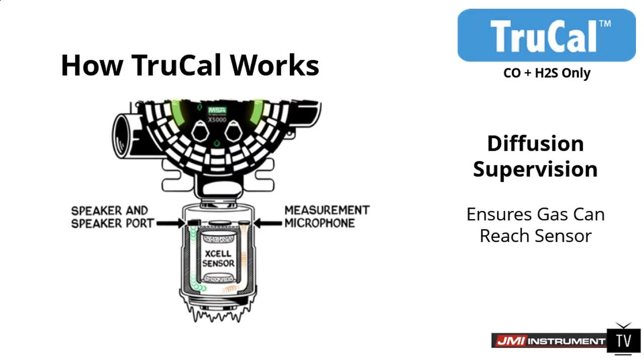And when diffusion supervision picks this up, it's going to need 4 consecutive failures. So when TruCal does that pulse check every 6 hours, in a 24-hour period, it has to fail all 4 of them for us to go into diffusion supervision fault and alert any user that the sensor is blocked. But with this portion enabled, we just recently changed to a 2-year calibration. So we can actually have our CO and H2S sensors go a full 2 years without needing to be calibrated, if you're monitoring the TruCal and/or the pulse check, and you're monitoring the diffusion supervision. That's big news in the world of electrochemical sensors.